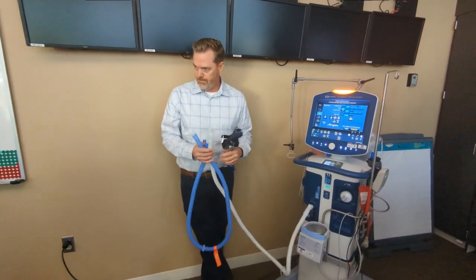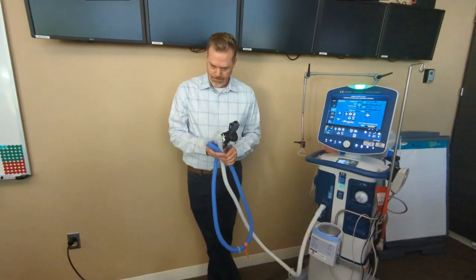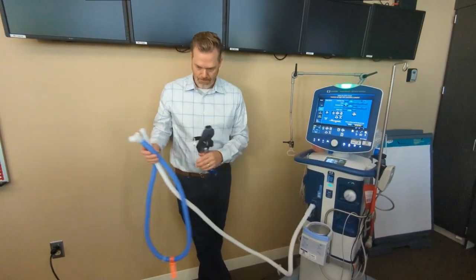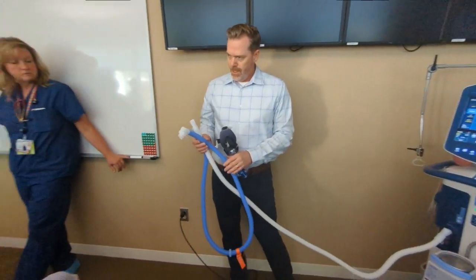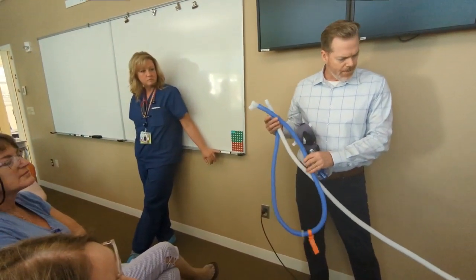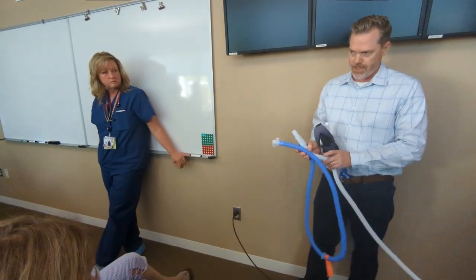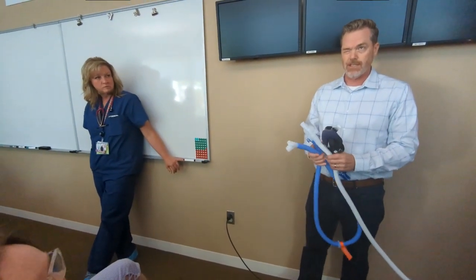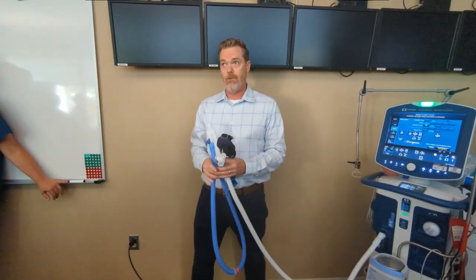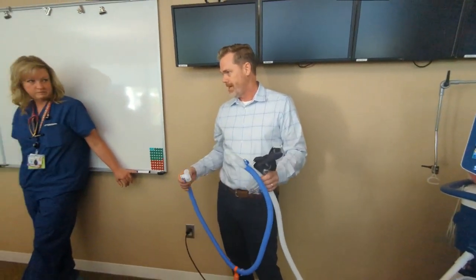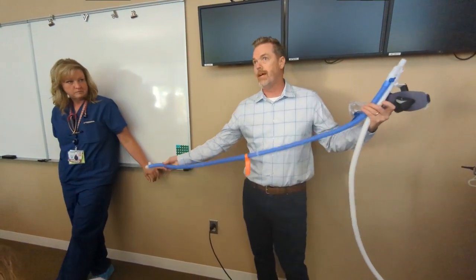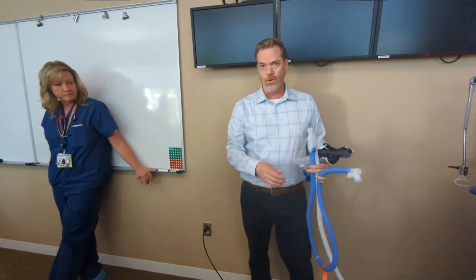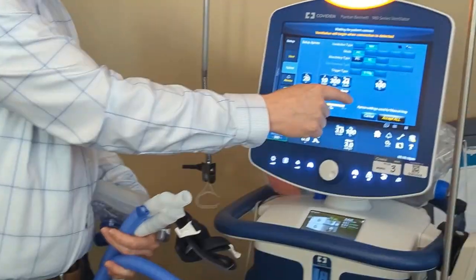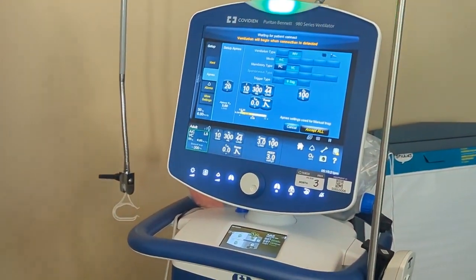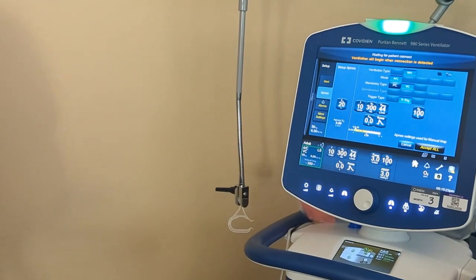Right. Is this similar on the Draeger? The same sensitivity settings? Because on the Draeger we have a NIV too, right. But how is that? I was thinking your sensitivity on the Draeger I thought was backwards from this one. I thought on the Draeger, when you turn the sensitivity up, it's more sensitive. On this one, sorry, yeah, it's less sensitive, because it's going to default to a flow trigger. So it's saying the higher that number is, the more flow it's going to take to trigger.